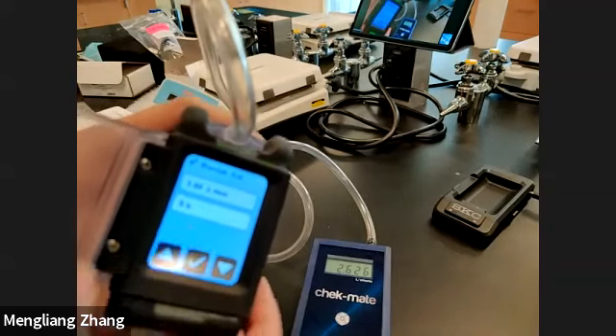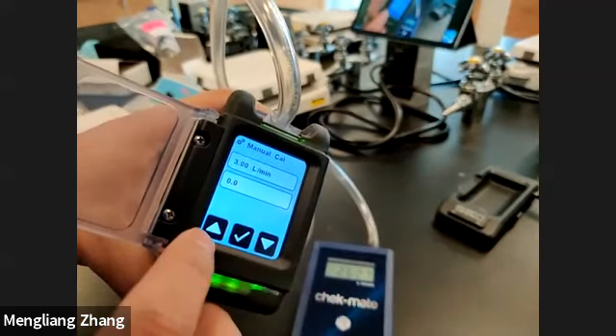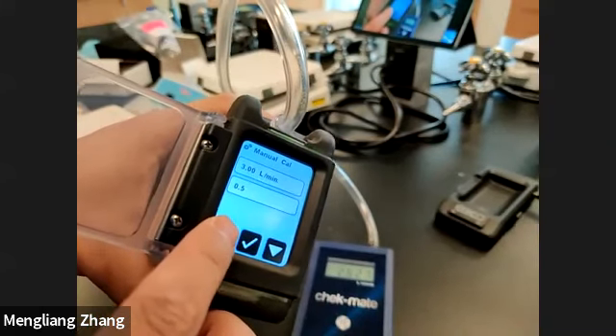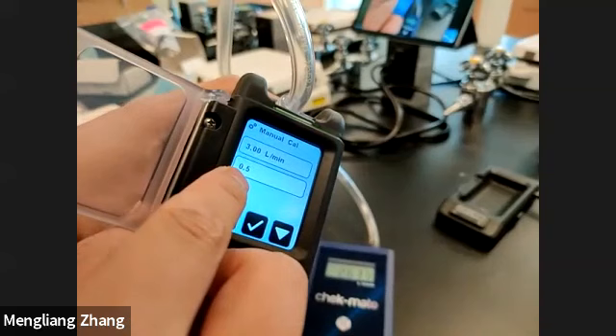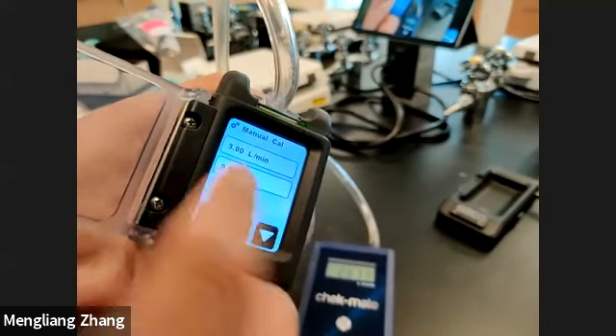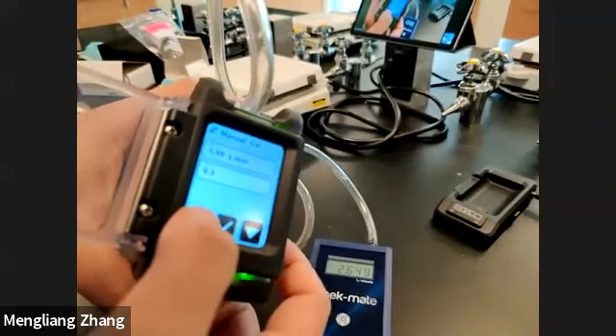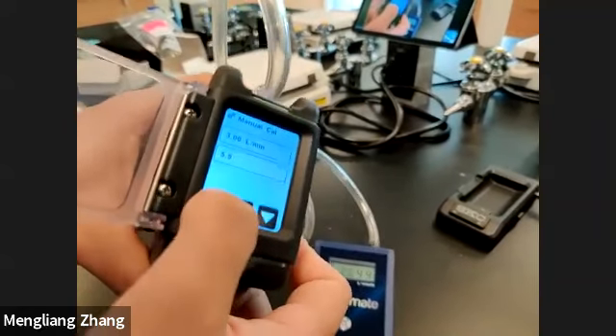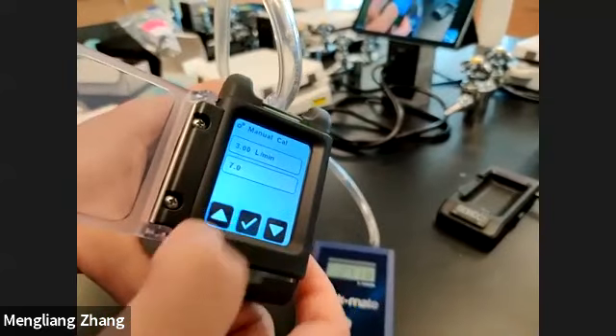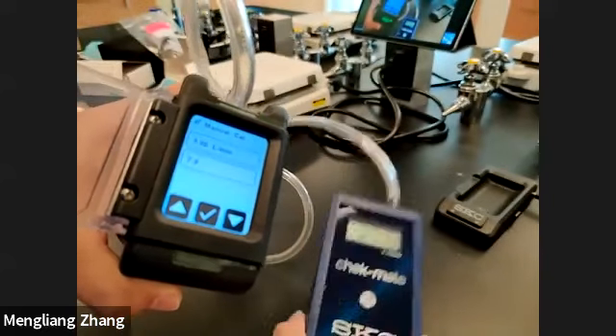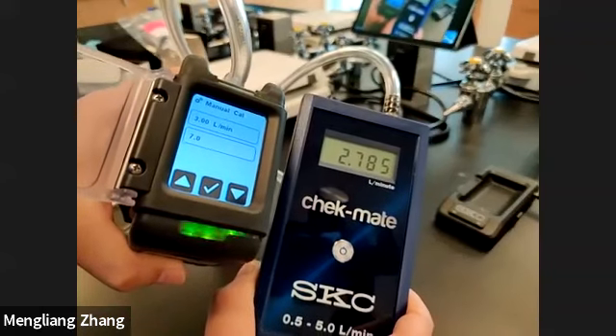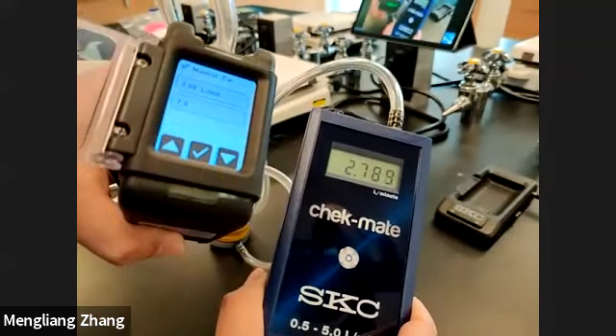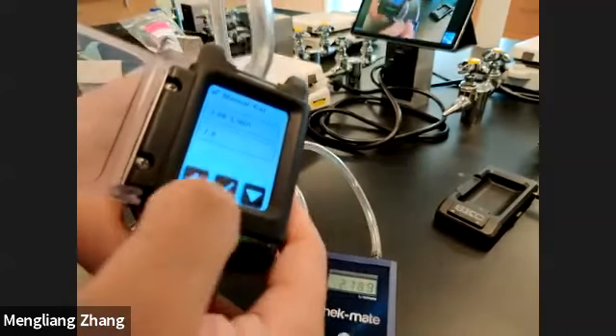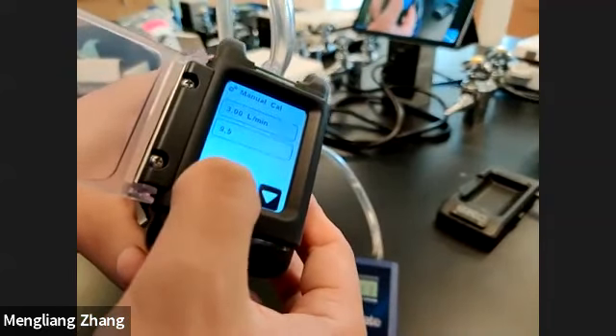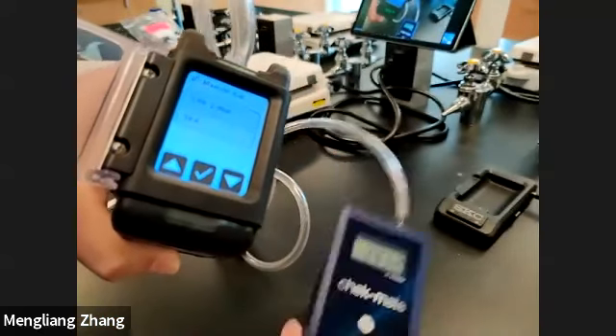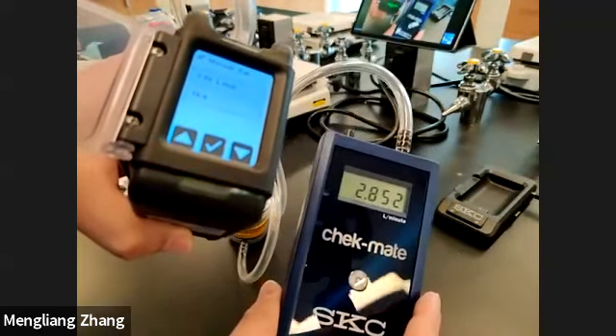So what we need to do is to increase the airflow on the screen. We just press the increase button. You can see there is a factor in the second row. Now it's increased by 0.5. According to my experience, you probably need to increase this a bit. Then you can see from the other screen the real airflow is increasing. However, it's still not 3.0 liters per minute yet, so we need to increase this more. We just press increase. Okay, it's 2.8.